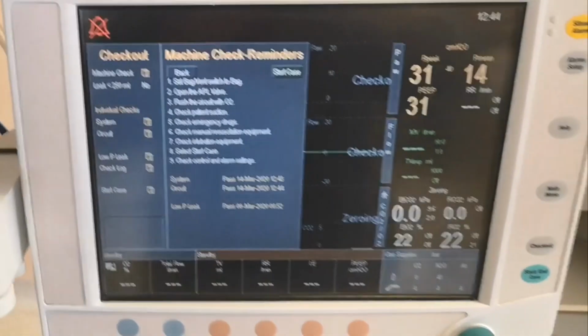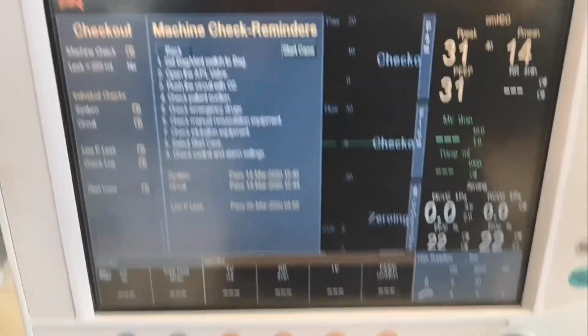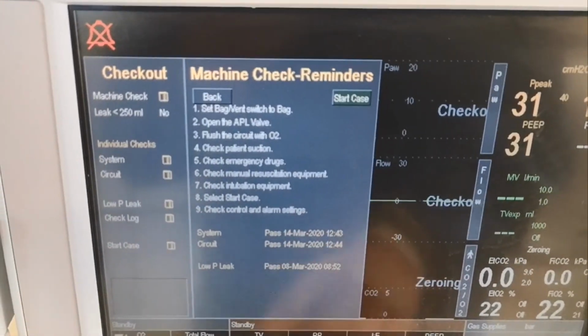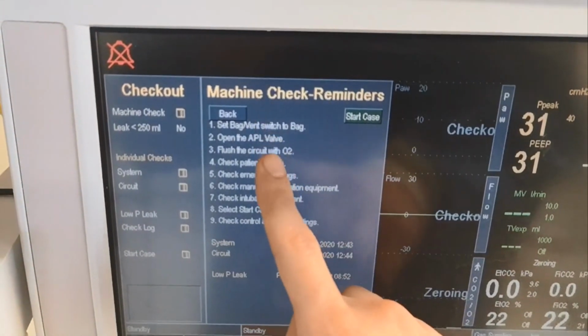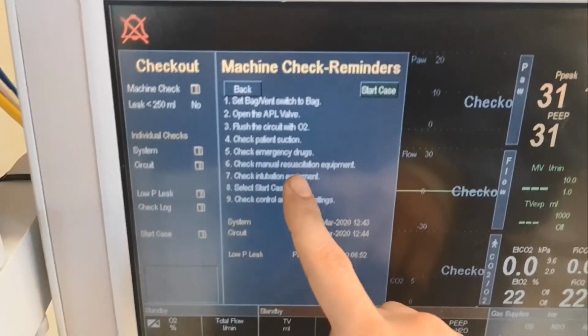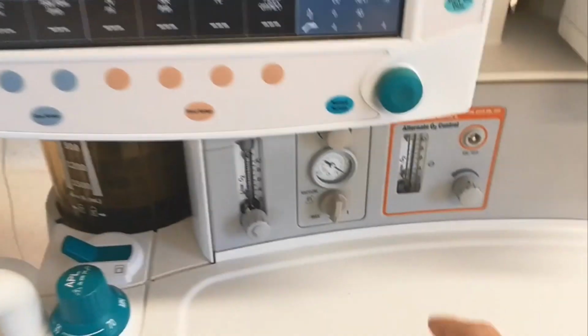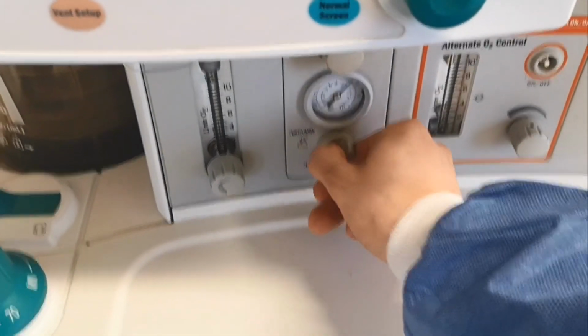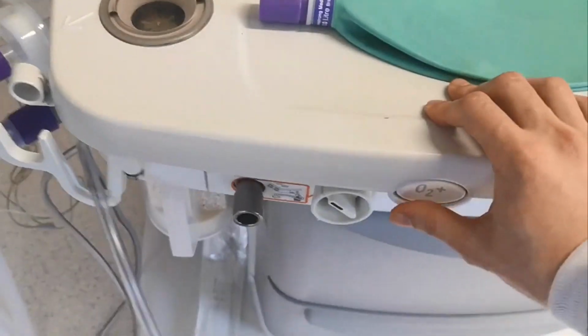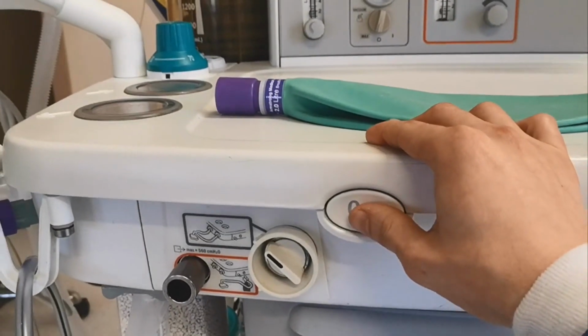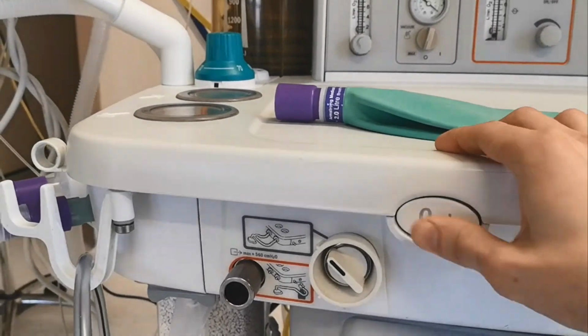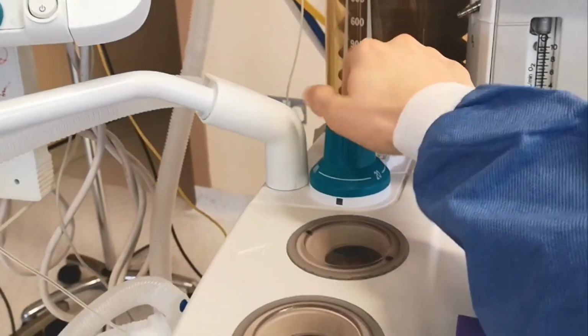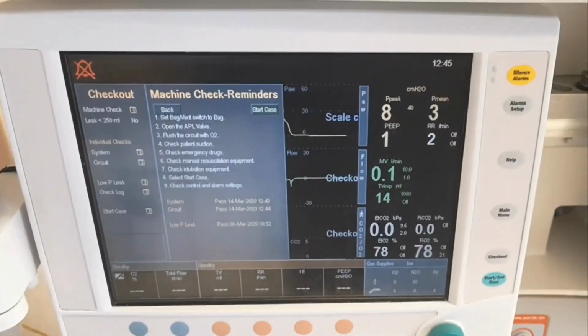Now, perfect. We have completed the check. All right. So now it's asking you to do another few checks, but basically you just have to check if the suction is working, which it is, and if the oxygen bypass switch is working, which it is, and that's it. So you just go back to minimum on the APL valve, you open it, and there you have it. You have a machine ready to deliver.